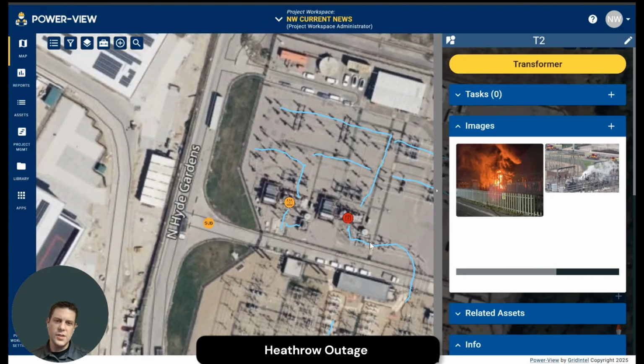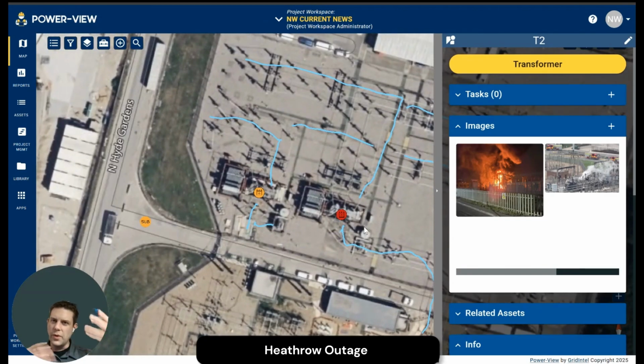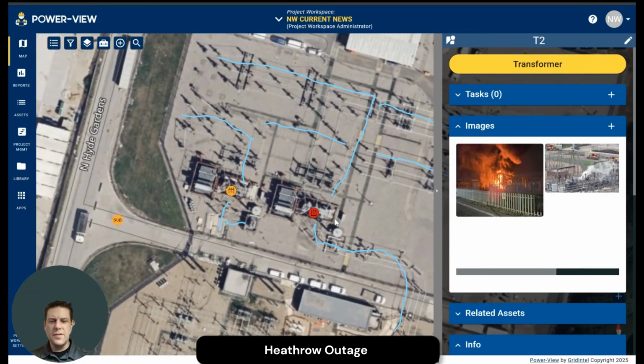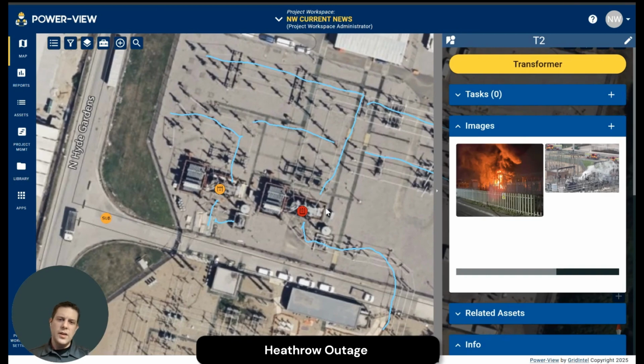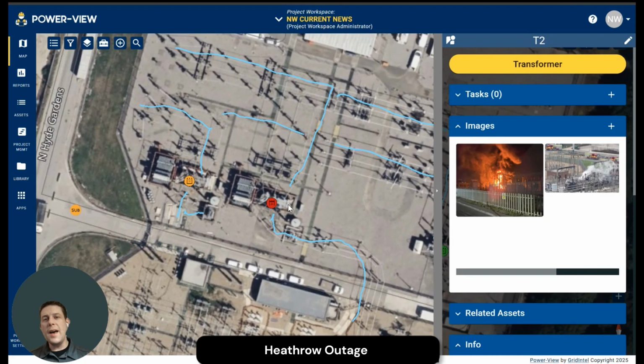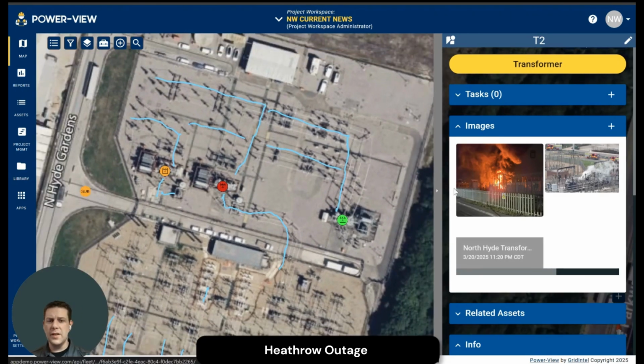The idea is to dissipate the heat quickly, so there are cooling tanks with oil that circulates. It's interesting how over time these systems can degrade and break, for a variety of reasons - this can even happen with new transformers. I'm not trying to assign a specific cause, but it comes back to extensive monitoring, root cause analysis, and having redundancies and resiliencies in place to help keep the lights on during these events.